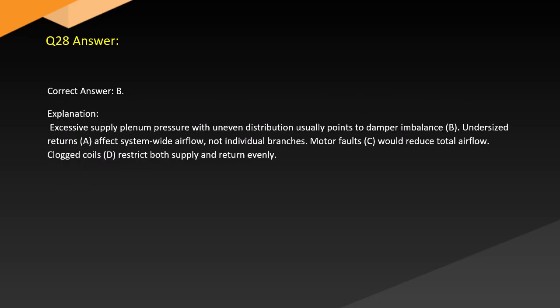Answer. Correct answer: B. Explanation. Excessive supply plenum pressure with uneven distribution usually points to damper imbalance. Undersized returns, A, affect system-wide airflow, not individual branches. Motor faults, C, would reduce total airflow. Clogged coils, D, restrict both supply and return evenly.